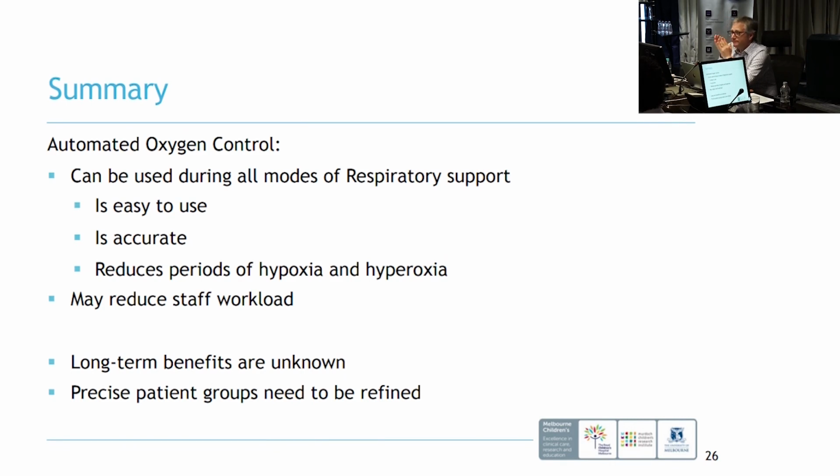Any other questions? Yeah, just the proportion of rise in FiO2, is it proportional to the degree of drop? It depends on the algorithm, right? Because if it's from 95 gone to 60 versus 85. So the Oxygenie one, in my experience, you probably know the engineering better than me. There's a background to how it works. Partly it's also where you are on the dissociation curve.